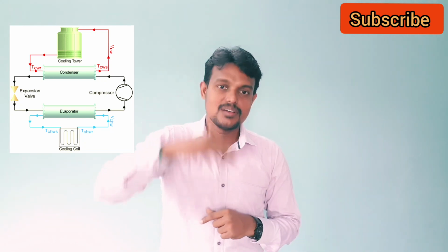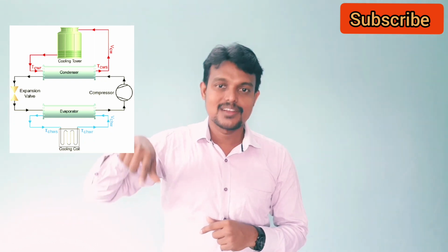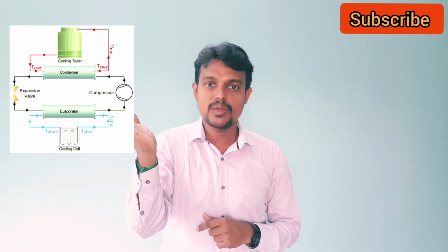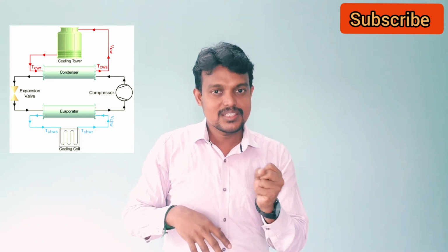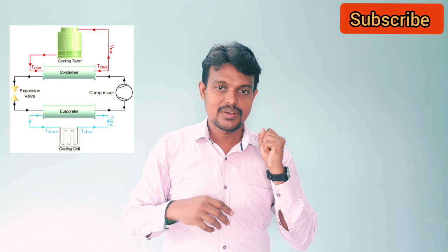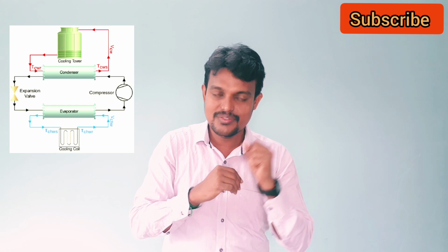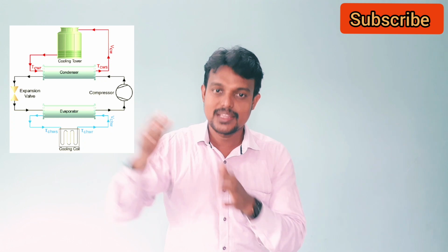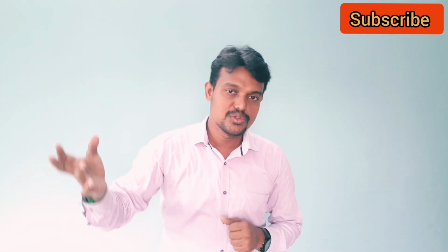On the other side, the water from the cooling tower comes inside the condenser coil, absorbs all the heat from the refrigerant, and goes back to the cooling tower, where the heat is released into the atmosphere.